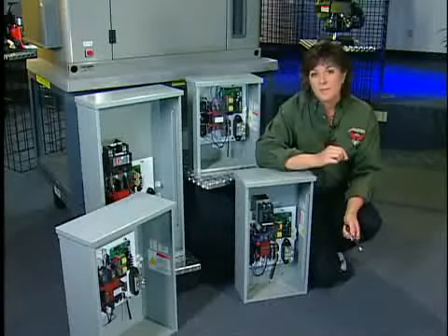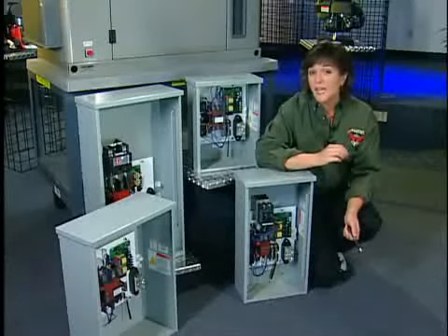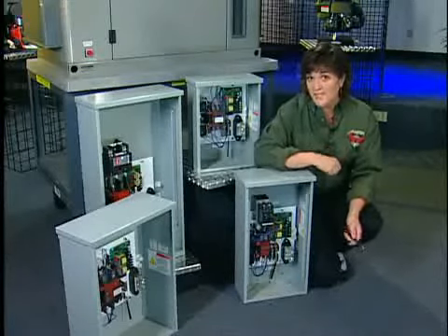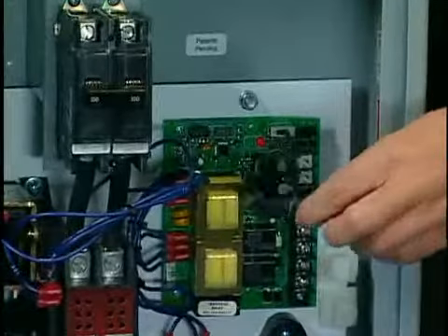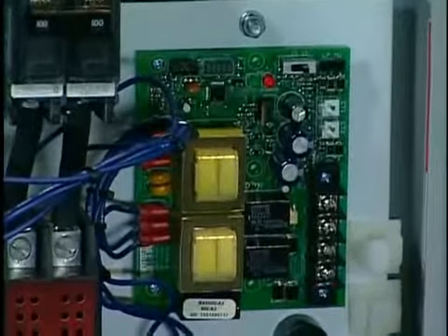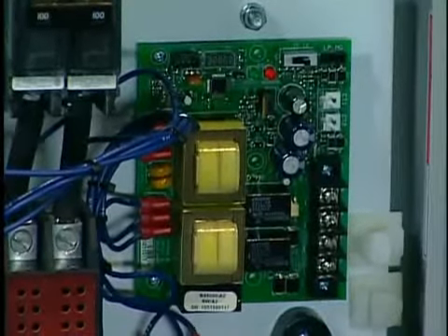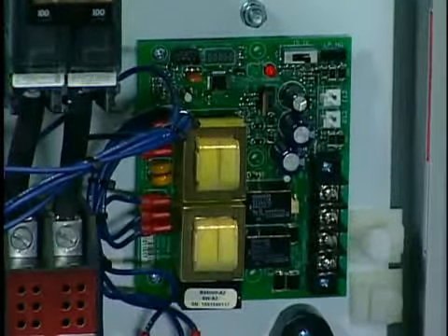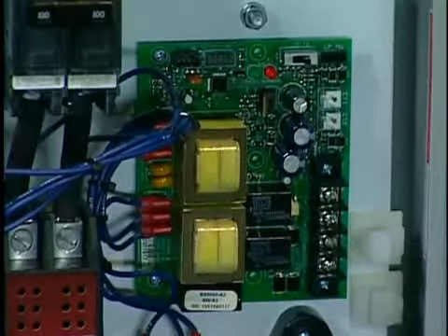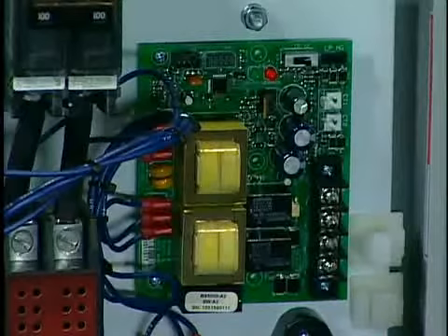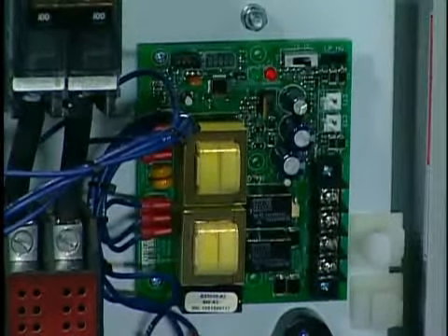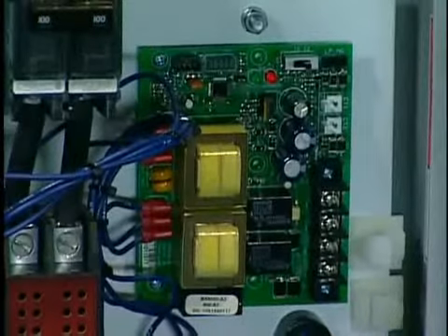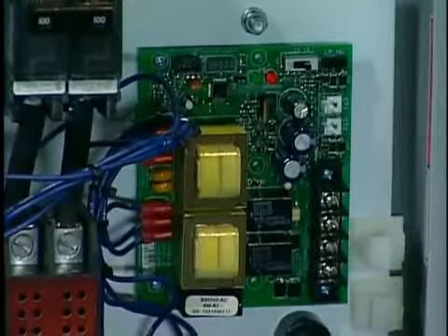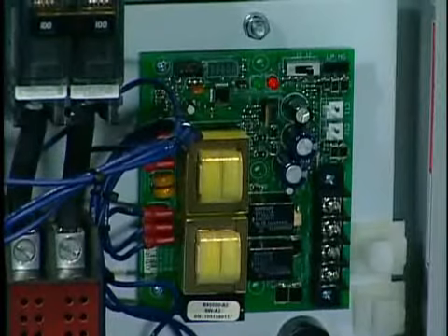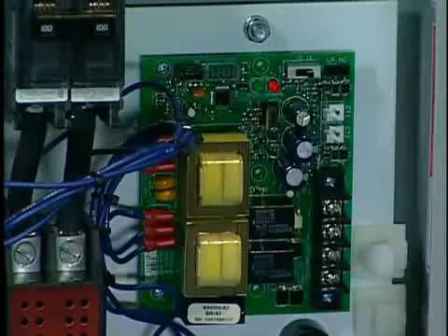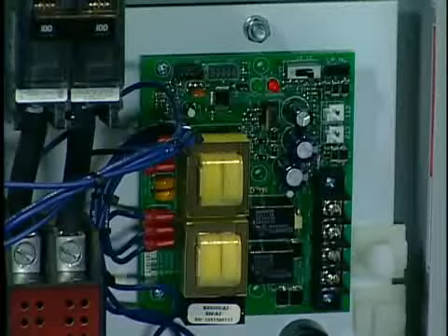The next two items are transfer switches that incorporate an air conditioning control module, or ACCM. This unit is designed to monitor the amount of energy it takes to start the air conditioning unit. During standby generator operation, when there is enough available power from the generator, the ACCM will allow the air conditioner to start. If at some point overall power demand exceeds the amount of power needed to start the air conditioner, the ACCM will prevent the air conditioner from starting until there is enough generator power.